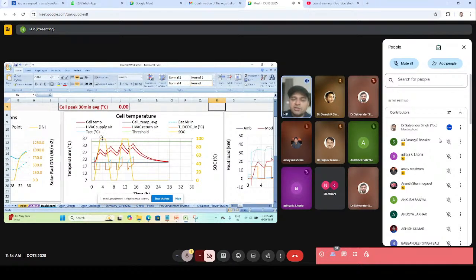When we give a rest, the cooling equipment is still running, taking out as much heat as it can, and that's why the cell temperature goes down. Then when we start discharging, shown as this yellow line, the cell temperature starts rising again. It doesn't mean cooling isn't happening; cooling is happening, but not all the heat can be extracted. So it keeps rising, then there's another rest period, and it keeps rising again.